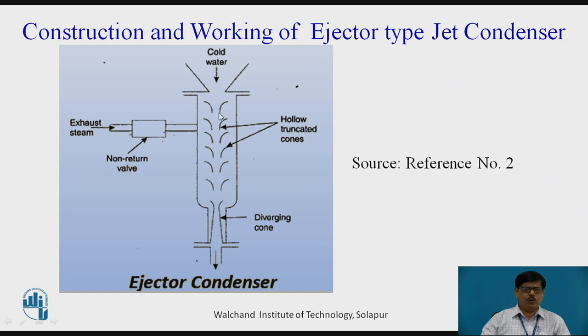When the cooling water flows through these converging cones, the velocity or kinetic energy of this cooling water will increase and the pressure inside this particular central tube will reduce. This reduction in pressure will cause the exhaust steam from the turbine exhaust pipe to enter through the non-return valve into this central tube. Inside the central tube, the exhaust steam surrounds the water, and the cooling water and exhaust steam coming out of the turbine will be mixed inside this, causing the condensation of exhaust steam.